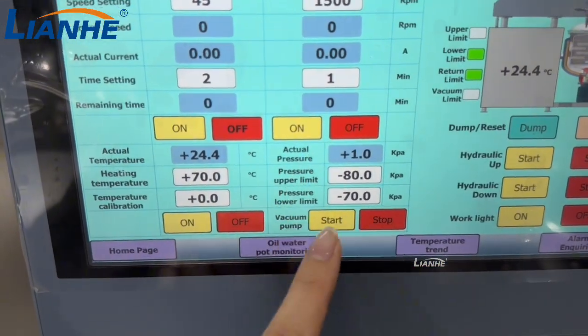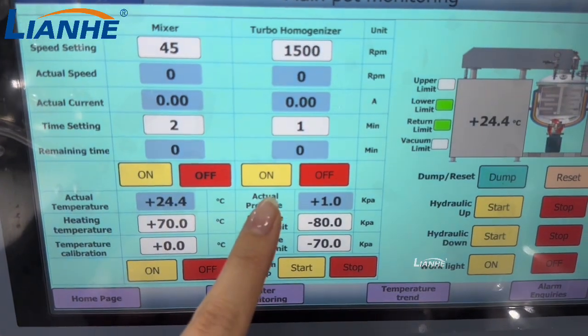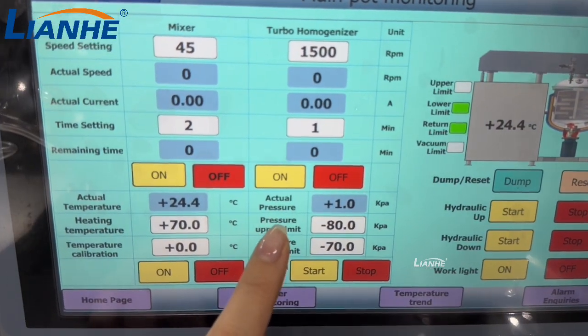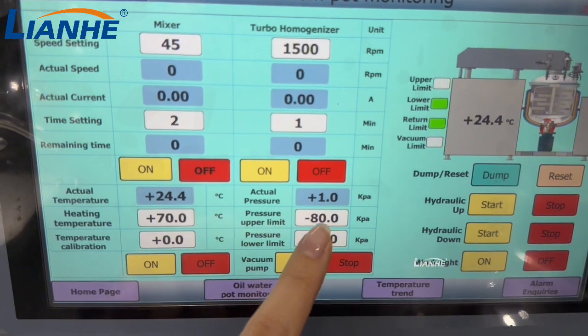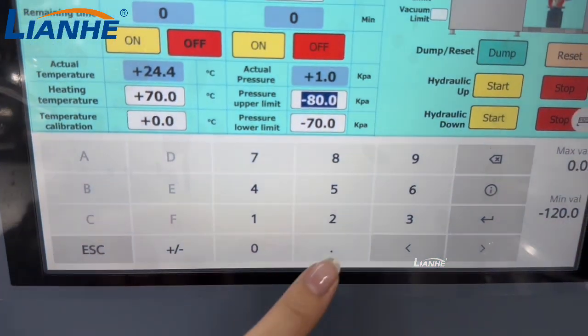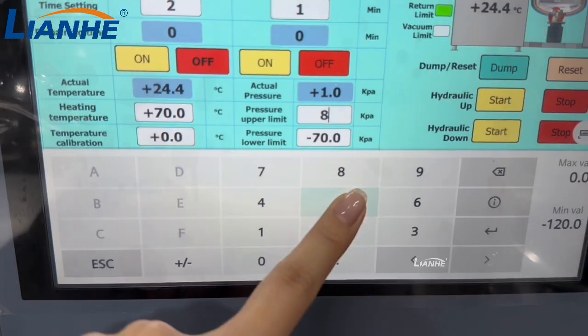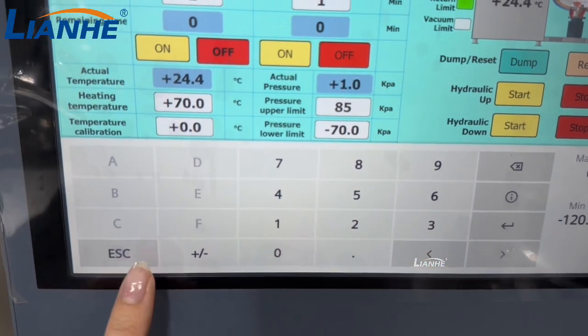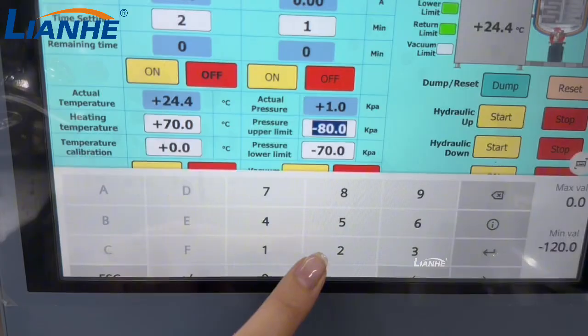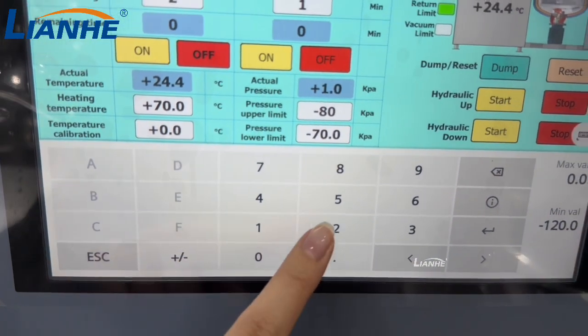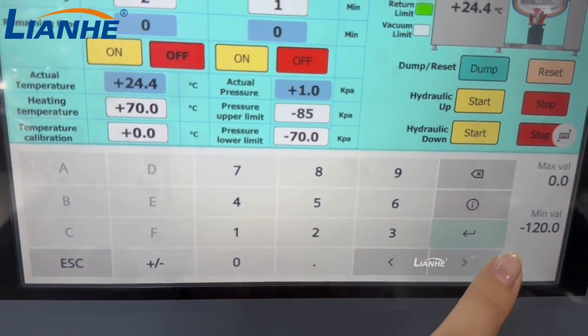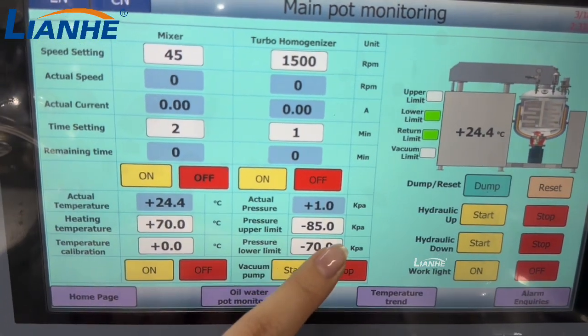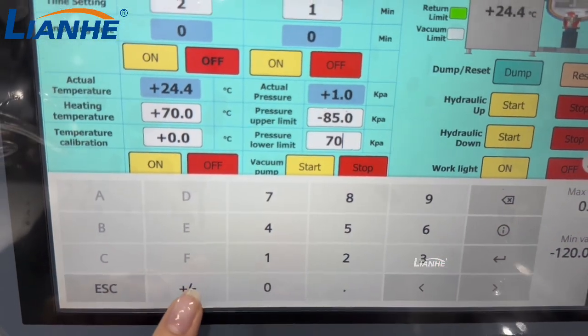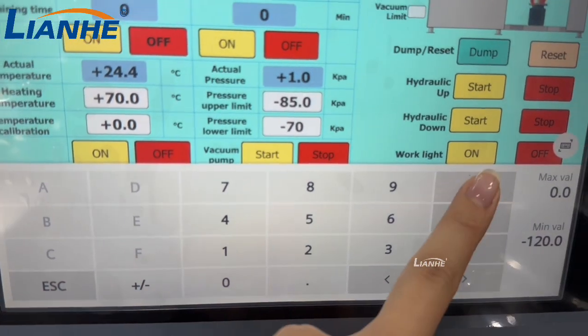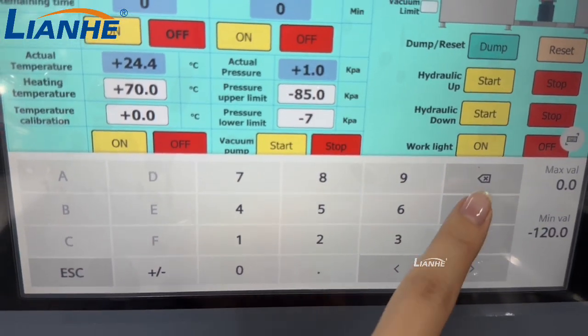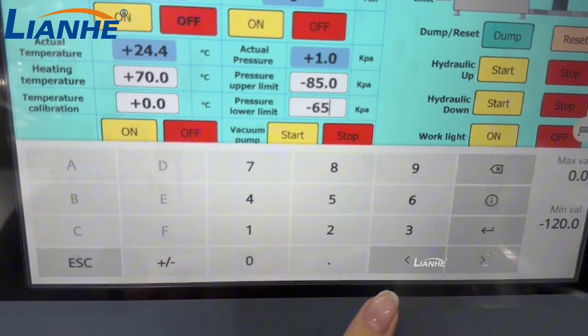And then you can see here is the vacuum function, where the actual pressure is displayed, and then the pressure upper limit, we can set like minus 85, like here. And then the pressure lower limit can also be selected, like minus 65, for example.